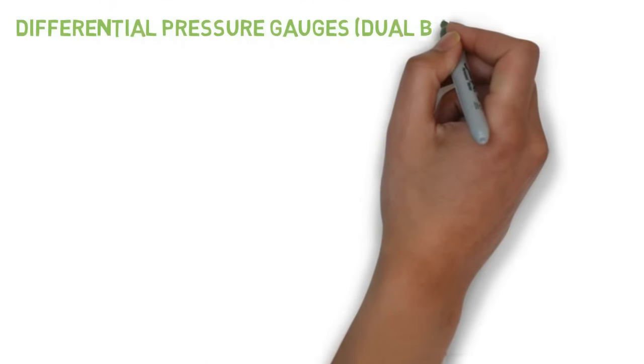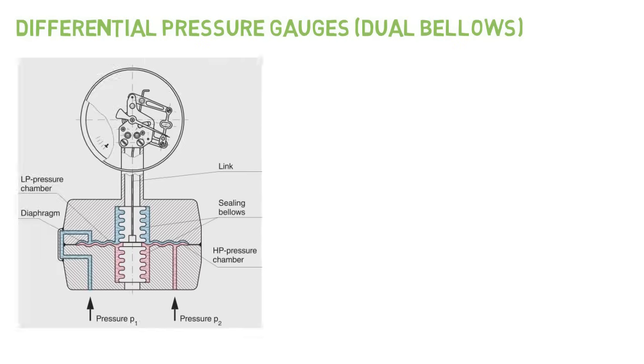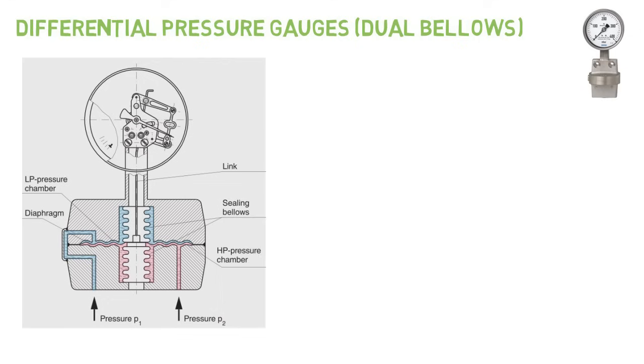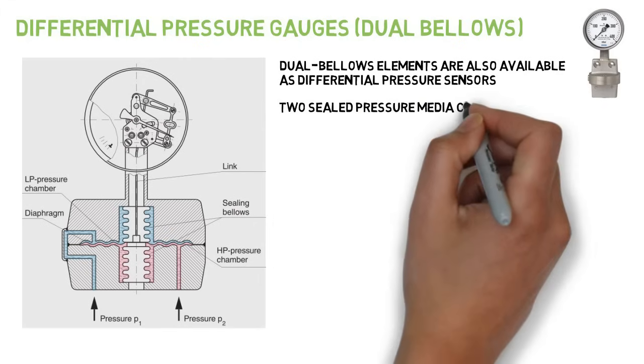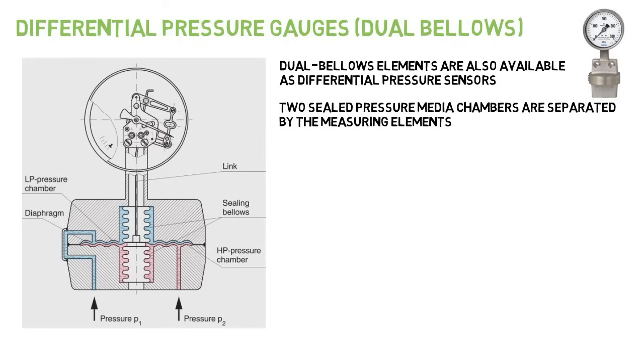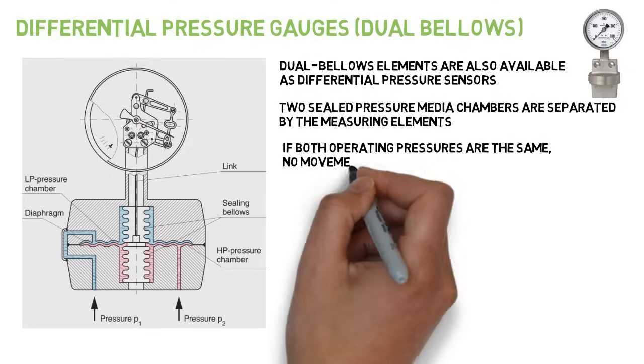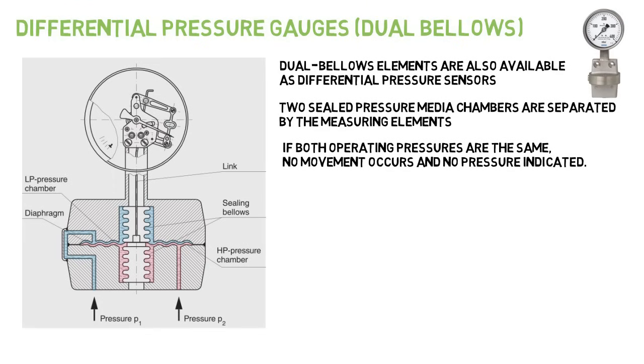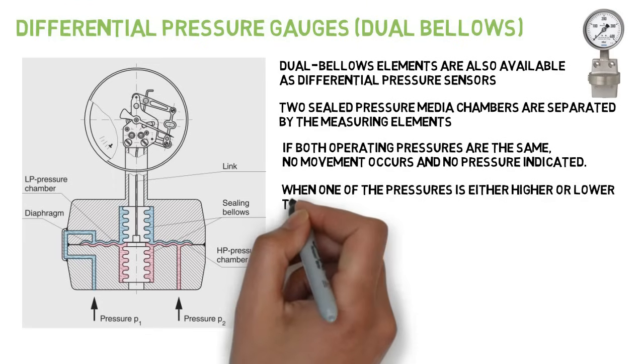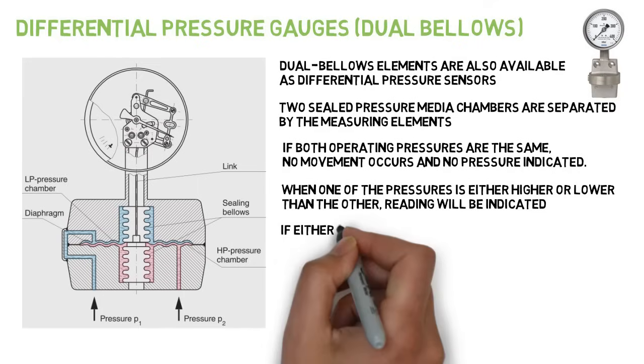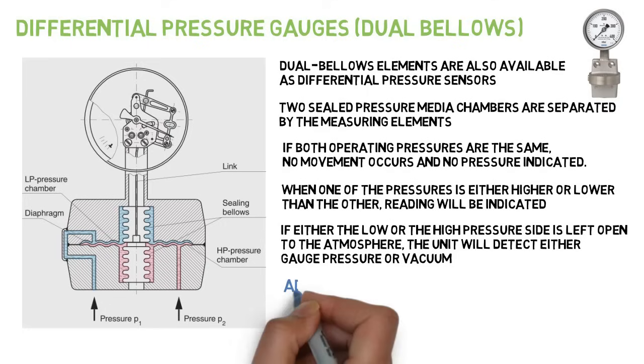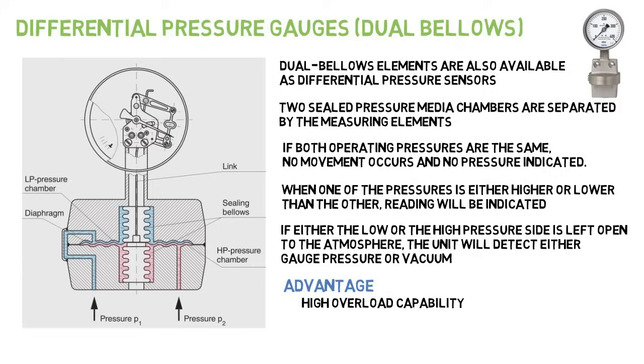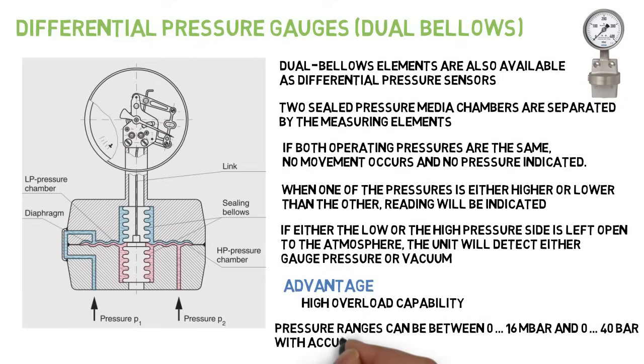Differential pressure gauges using dual bellows. Dual bellows elements are also available as differential pressure sensors. Two sealed pressure media chambers are separated by the measuring elements. If both operating pressures are the same, no movement of the measuring element occurs and no pressure will be indicated. When one of the pressures is either higher or lower than the other, a differential pressure reading will be indicated. If either the low or high pressure side is left open to the atmosphere, the unit will detect either gauge pressure or vacuum pressure. Pressure ranges can be between 0 to 16 mbar and 0 to 40 bar, with accuracy classes of 0.6 to 2.5.